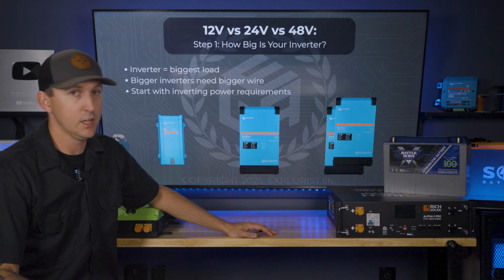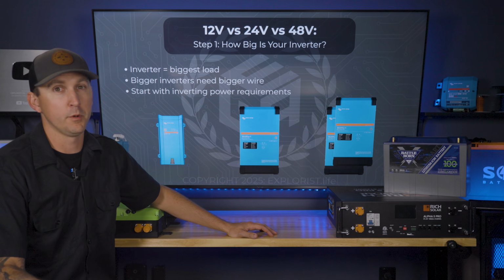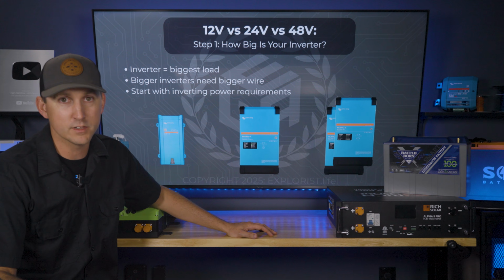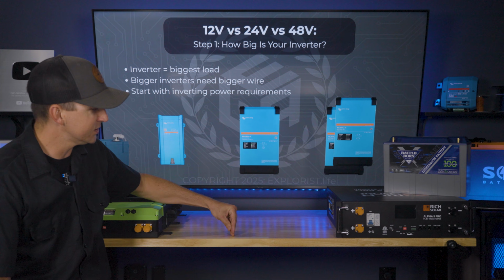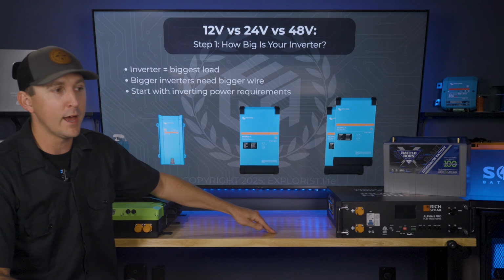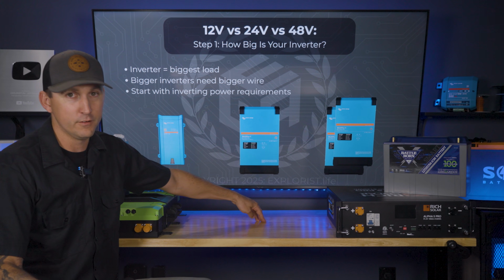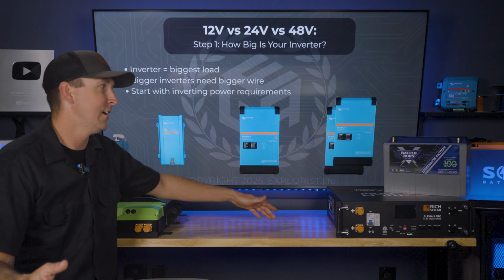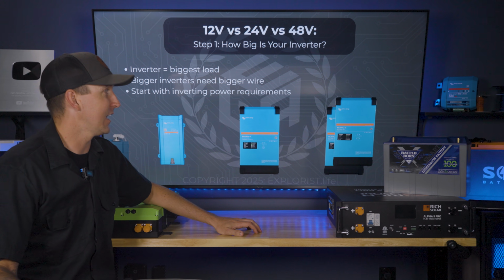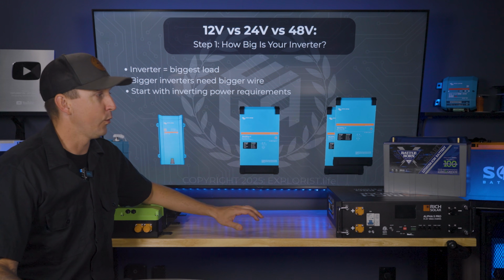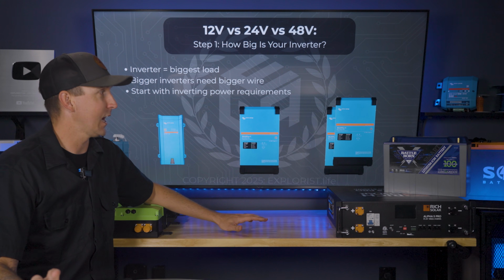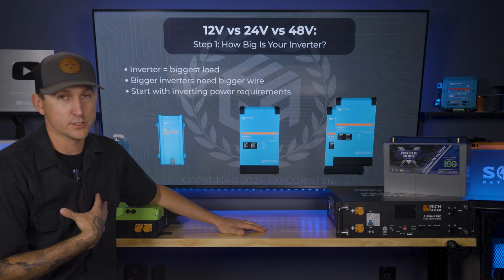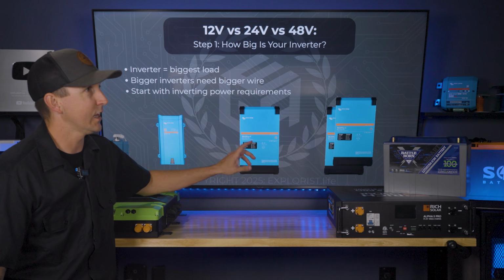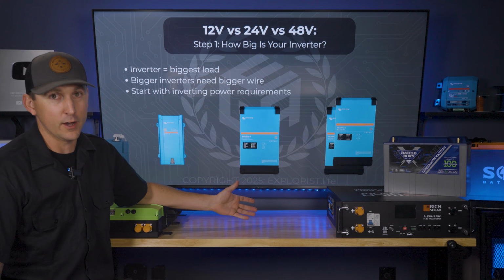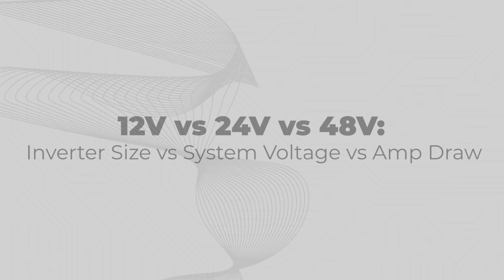Now, are there DC loads in an electrical system? Yeah, sure, but most of them are pretty small most of the time. And unless you're pushing every single one of your DC loads to its absolute max and pushing your inverters to their absolute max, you don't really have to take that into consideration. So I like to only focus on inverter size whenever I'm making a determination on the battery bank system voltage. Here's the numbers behind what I'm talking about.